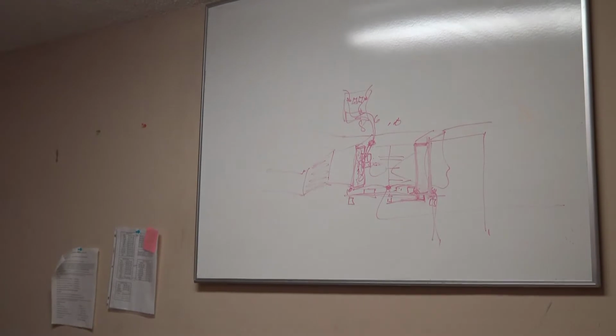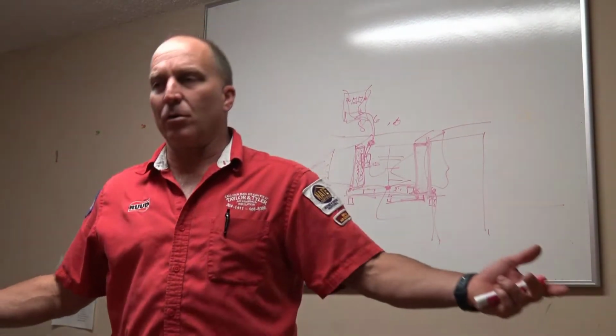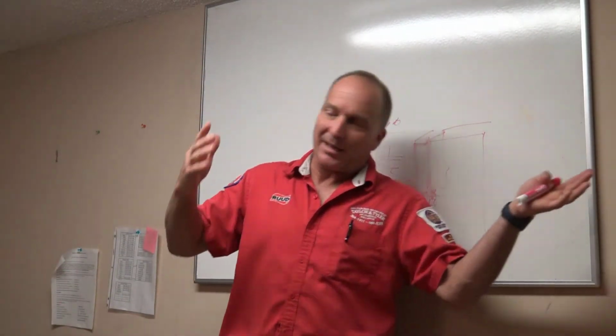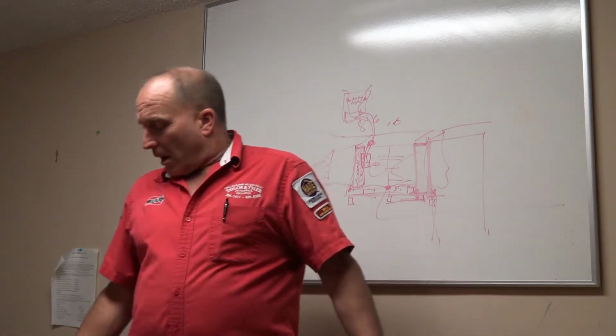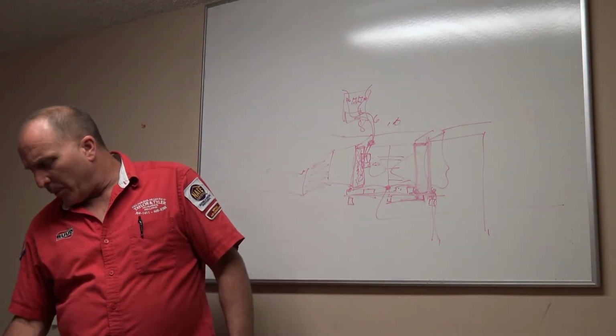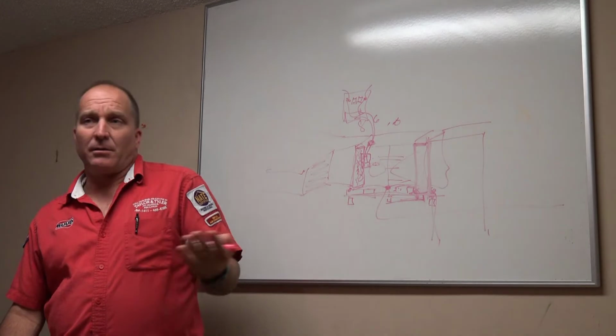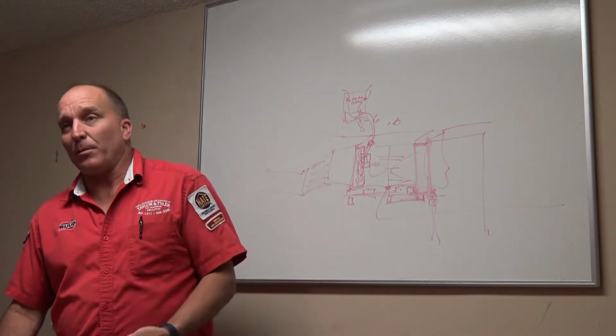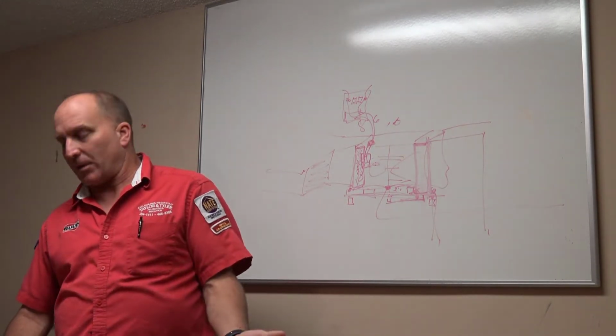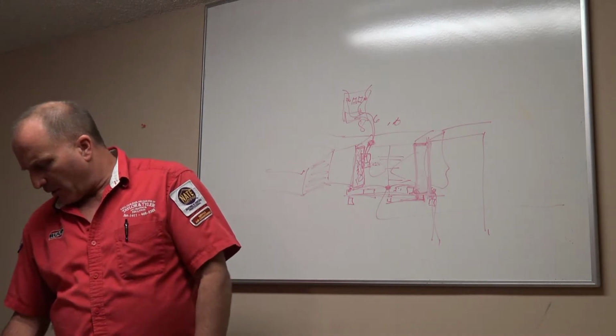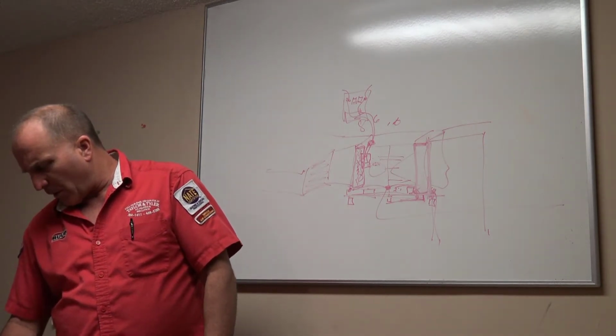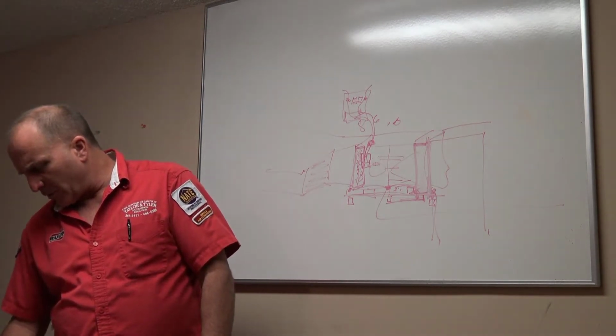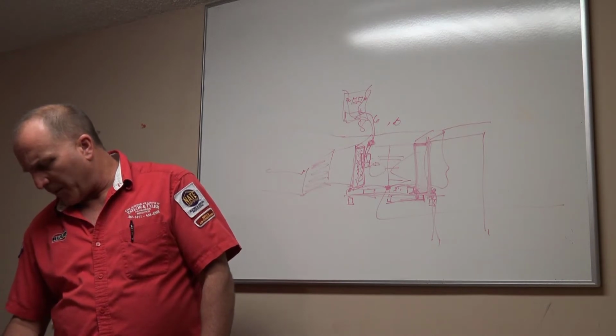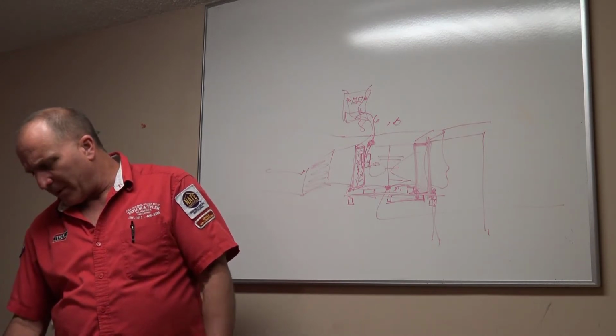So heat sequencers, when you apply power to them, close the heat sequencer, which turns the heating element on. These will be good or bad. You apply voltage, it closes. If you apply voltage and it doesn't close, replace your heat sequencer. All right. Turn on the heating elements. Check voltage across the heat sequencer, and the heat sequencer is working. All elements should draw amperage. Okay, simple means it works.